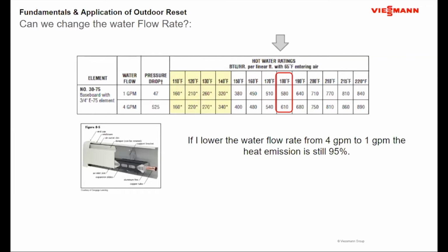So all of a sudden, if I'm trying to balance the system out and vary the flow rate, you'll find that I don't end up with a nice response, where I have a big change in the flow rate and get a corresponding change in the amount of heat coming out of the heat emitter. It makes it very difficult to control and deliver based purely on changing that flow rate.